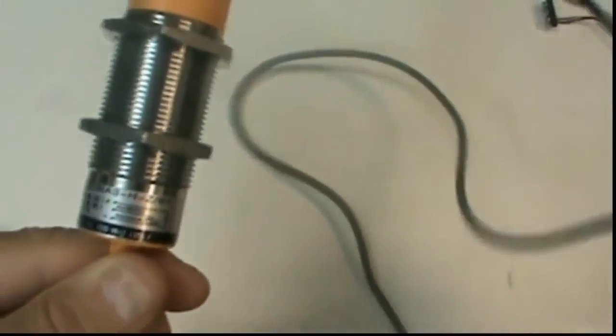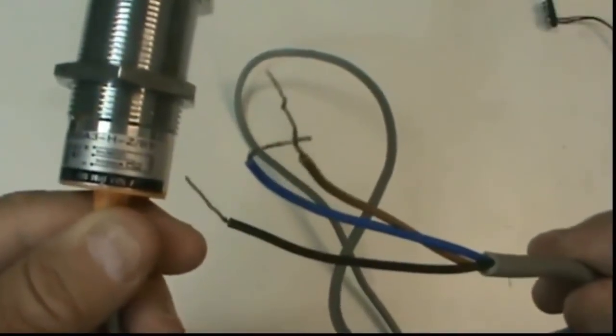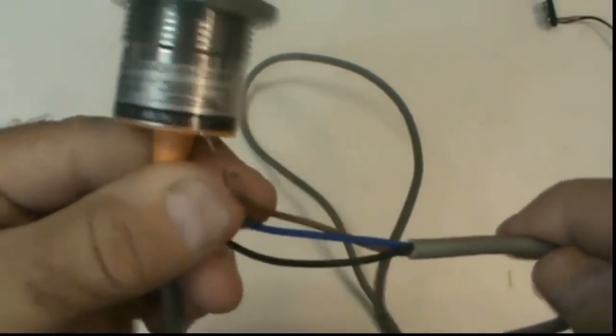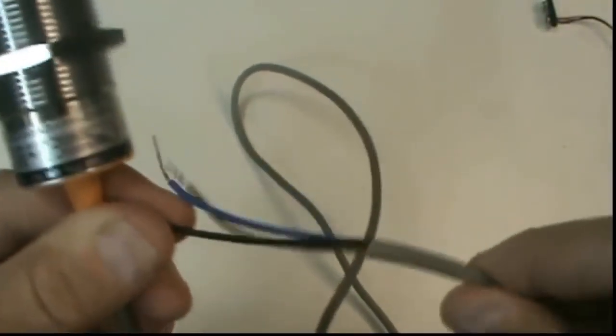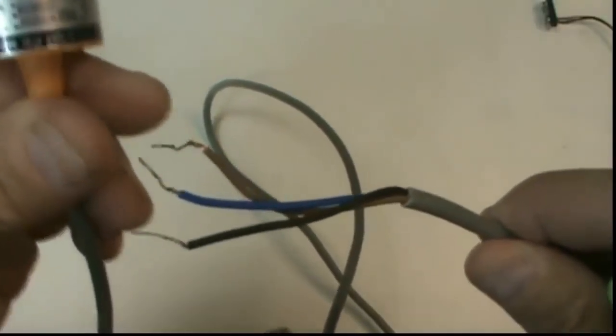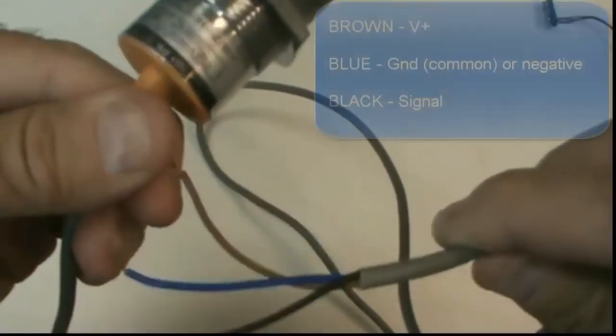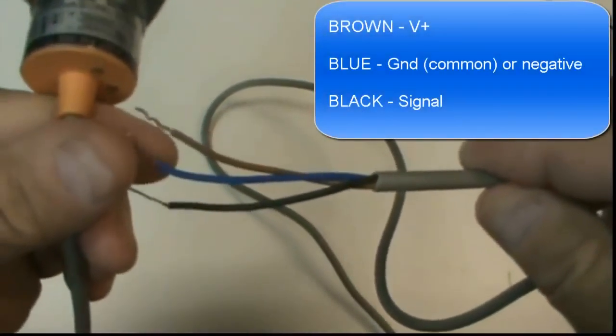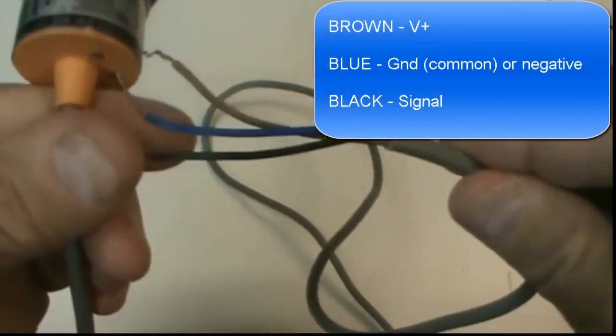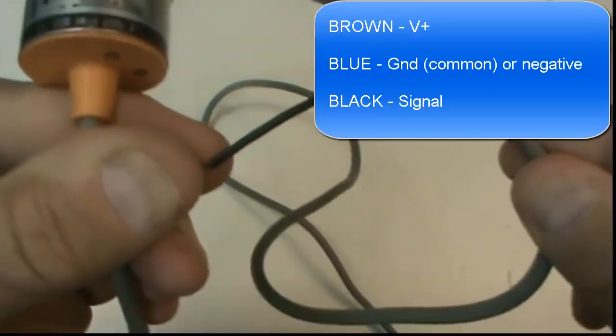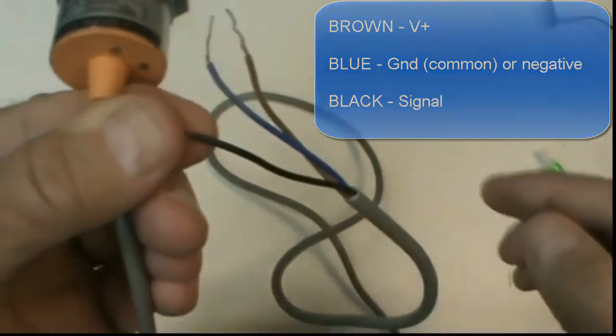The color coding for the sensor is a little unconventional compared to other things in electronics, but in sensors, our brown wire is our positive, our blue wire is the negative, and our output signal is the black wire.